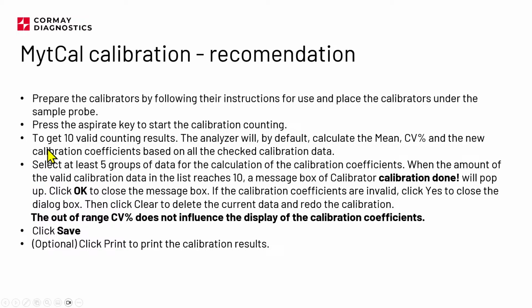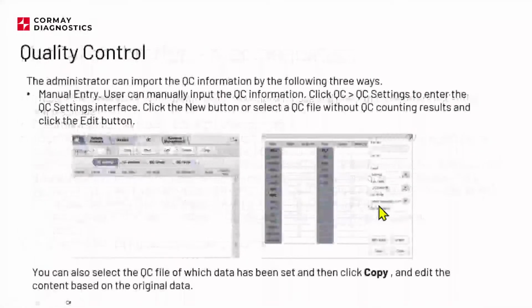Okay, there is also a recommendation to get 10 valid counting results, and then base it on all. Okay, select at least 5 groups of data. Yeah, so as I said, 5 groups, which will give you the best possible calibration CV value. And the out of range CV does not influence the display. Okay, click save. Yeah, so this is the last step to make sure that you will save the new coefficients.